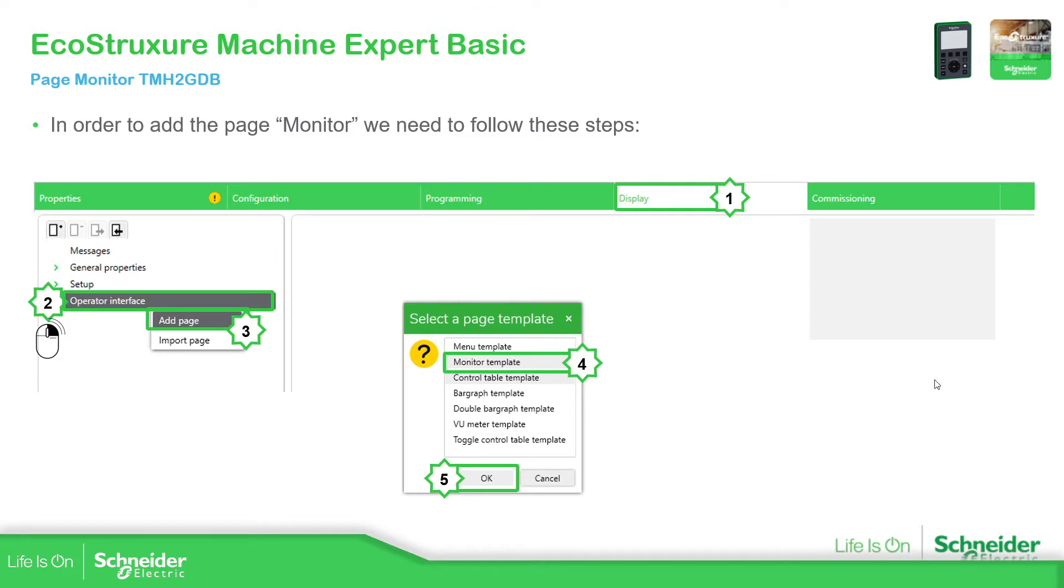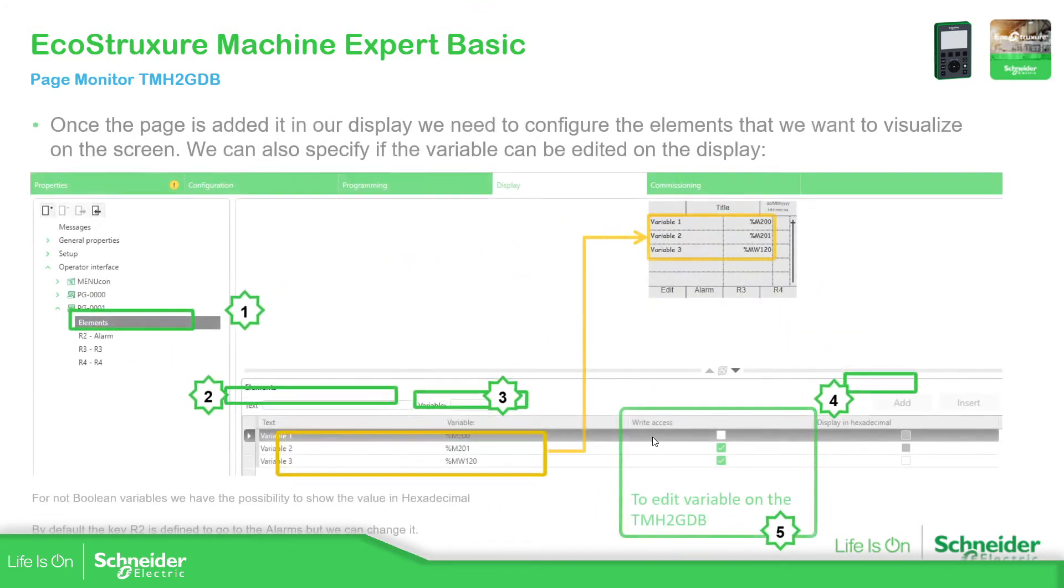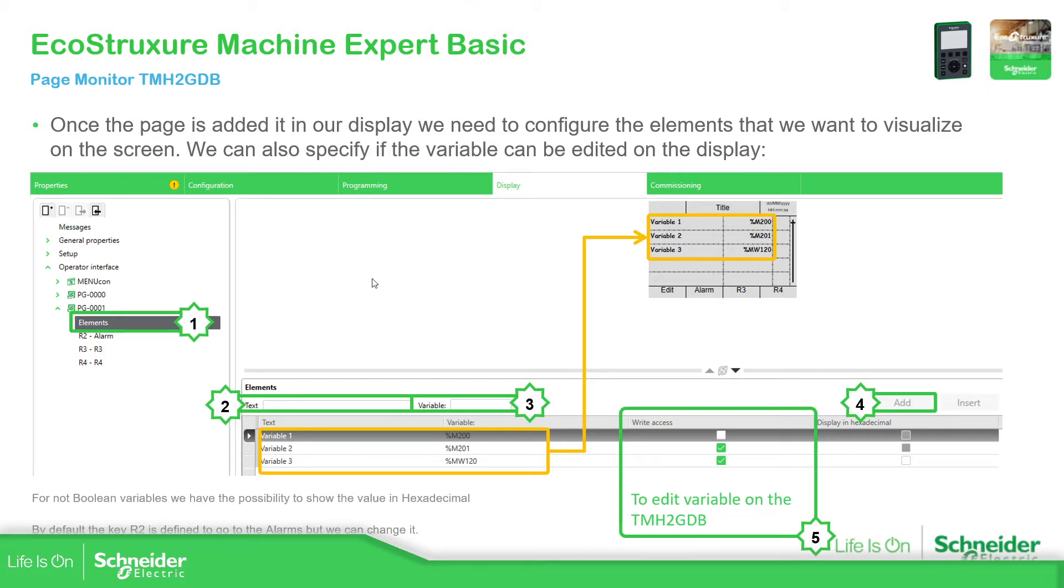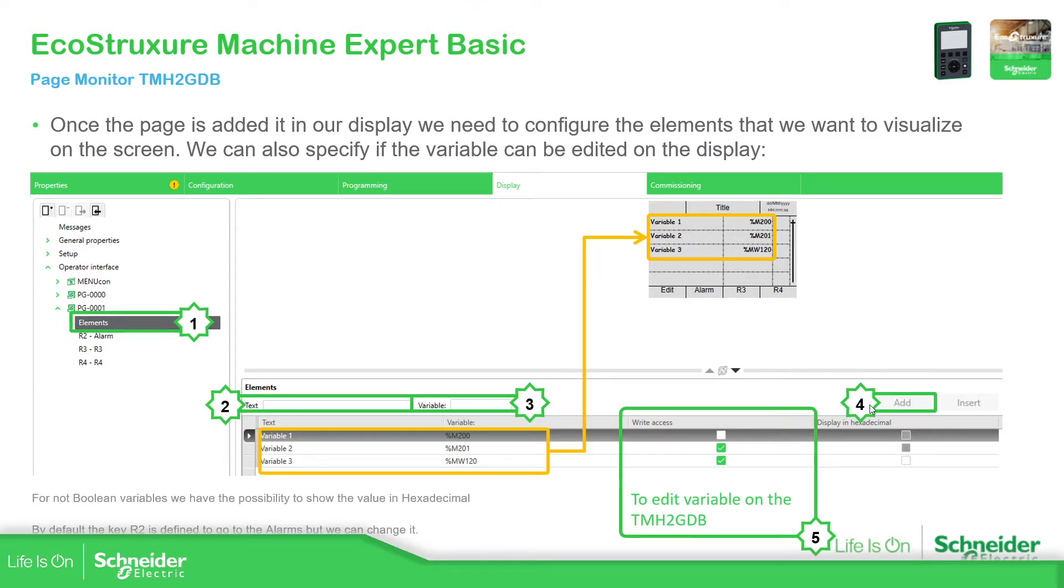How to add this monitor page is very simple. We just need to go to Display Operator Interface, right click over there, add page, select the monitor template and then okay. Then what we need to do is define the elements that we want to show on that page. Click on elements, define the text that you want to see over here in the left part, then associate the text with a variable. Then you will need to add this combination text and variable into the elements, and you have the possibility to specify if you want to edit that variable over here.